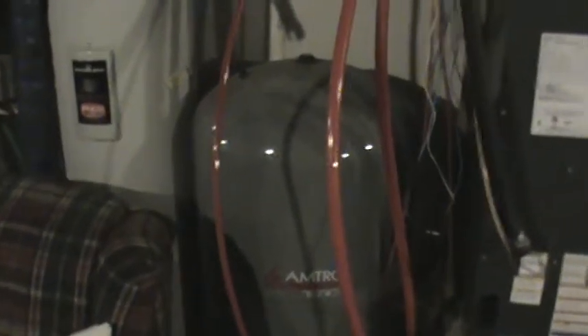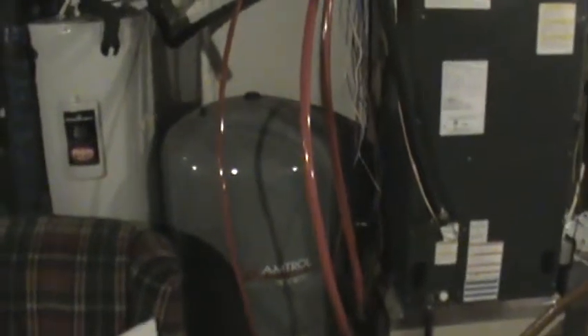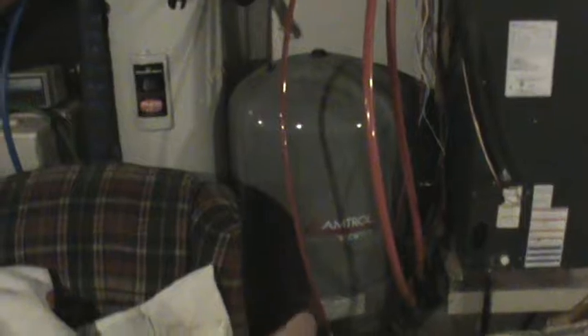Anyway, this is also an expansion tank right here. You saw the red expansion tank outside. This Amtrol expansion tank, you think, well, that's huge. It has a capacity of about 50 gallons. The reason for that is that my water storage system is 1,000 gallons of water that can be heated up. As that water expands, it also, of course, requires more volume. And so this is sort of an overflow tank, is the way you can think about it.